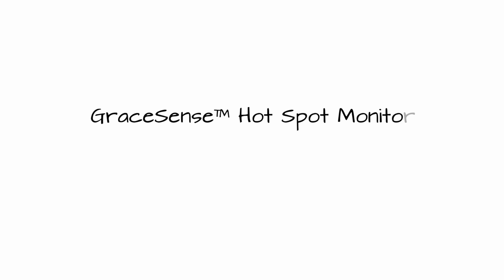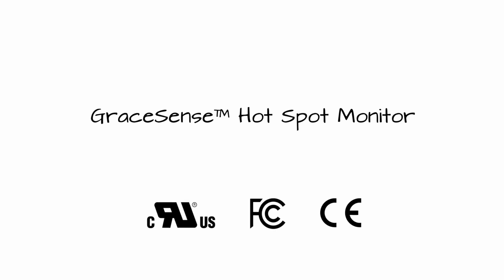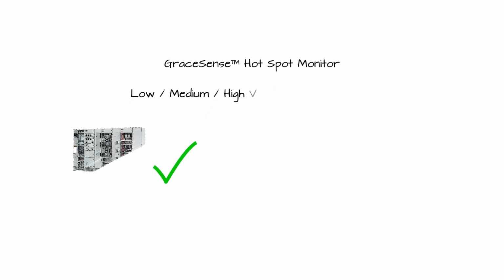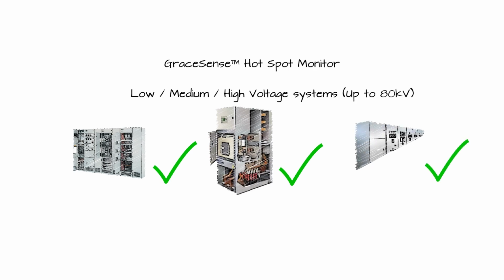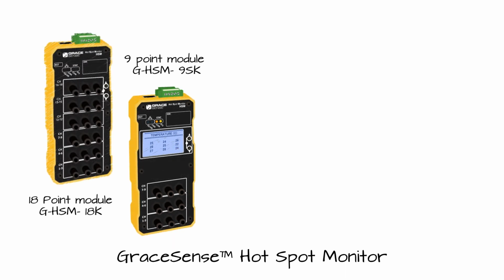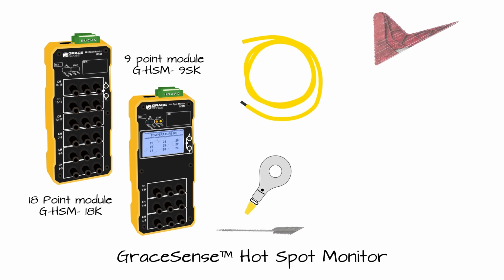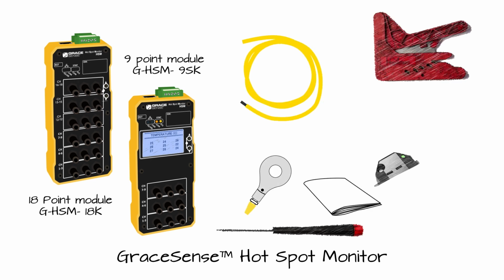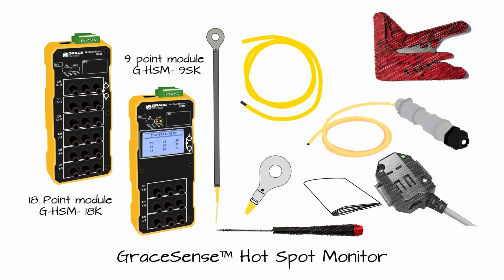GraceSense Hot Spot Monitor is a reliable and affordable solution for use in environments with low, medium, or high voltage systems. The HSM is available in 2 versions, either a 9-point module with a built-in LCD display or an 18-point module. The unit comes fully kitted with fiber probes, ring-style connectors, and an installation kit. Optional accessories include a Modbus current sensor, high-temperature probes, ambient measurement attachment, custom connectors, and fiber lengths of various sizes.